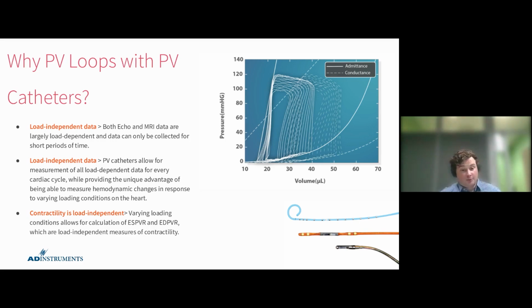The great thing about PV catheters is that you're able to record load-independent data. Essentially, with a PV catheter, you're able to get all of that load-dependent data for every cardiac cycle, while having the unique advantage of being able to measure hemodynamic changes in response to varying loading conditions, right? In a PV loop study with a PV catheter, this would most likely be an IVC occlusion.